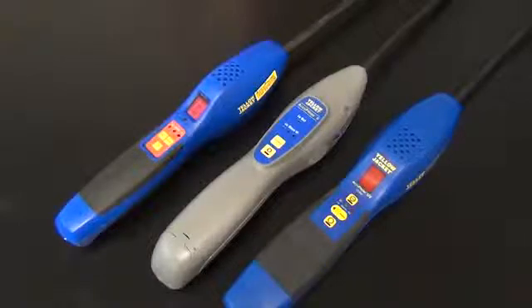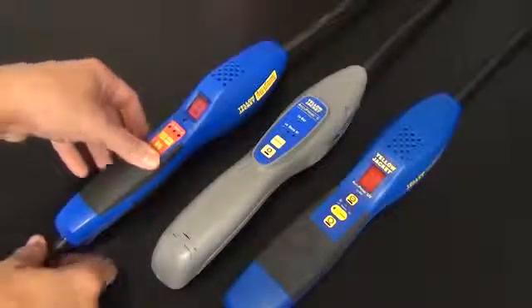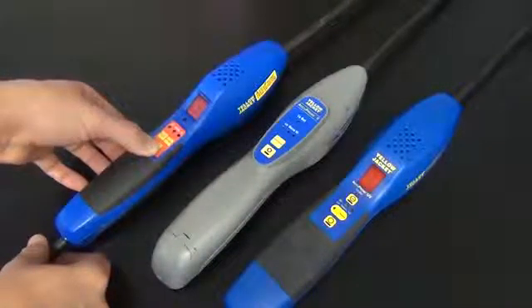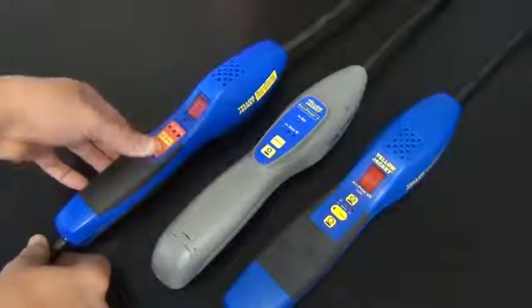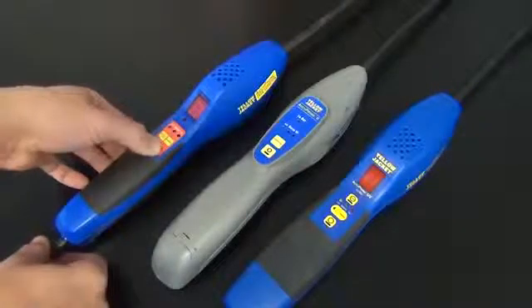If you have the original AccuProbe, you may have experienced this complaint. You try to turn on your leak detector and then try to turn it off, but it will not turn off. You have to remove your batteries to get it to turn off.